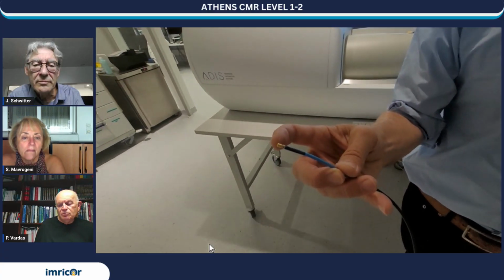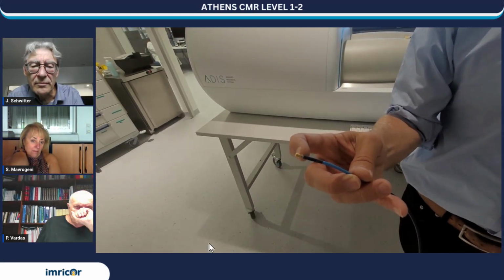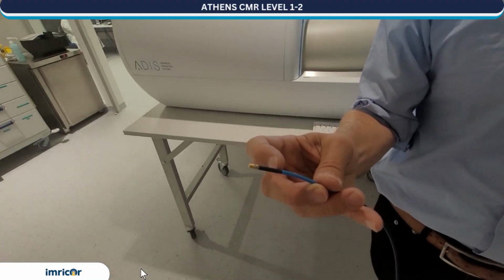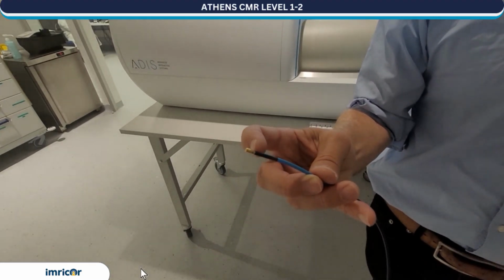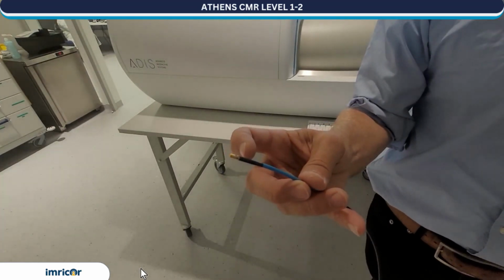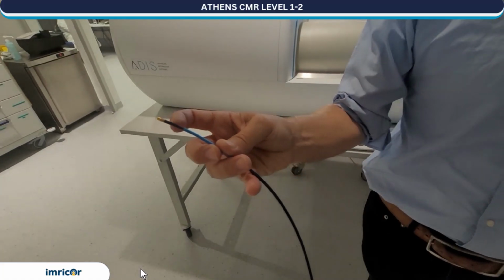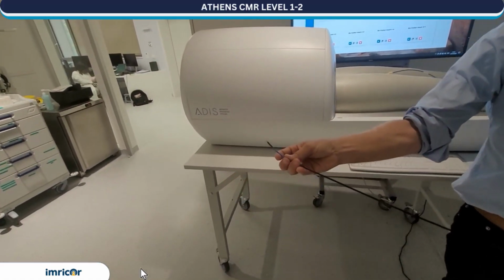Thank you, Jürgen. Good afternoon in Athens. It's my pleasure to show you the Imricor ablation vision MR catheter, which is made, as you can see, of a handle that you can use to bend the catheter. If you look at the catheter itself, it has different components. First of all, you can see two gold electrodes. The distal gold electrode has holes to perfuse sodium chloride during the ablation. Then there is a second recording electrode, and within that blue line, there are two receivers to be able to record the signal.